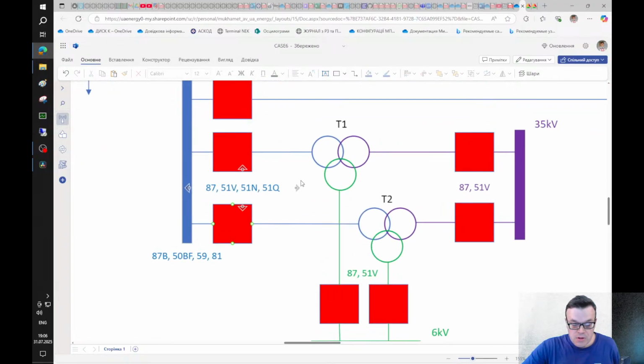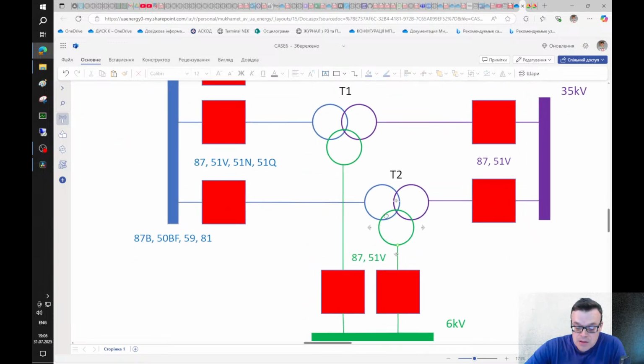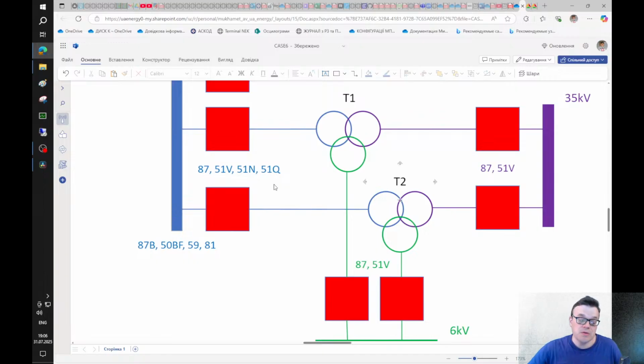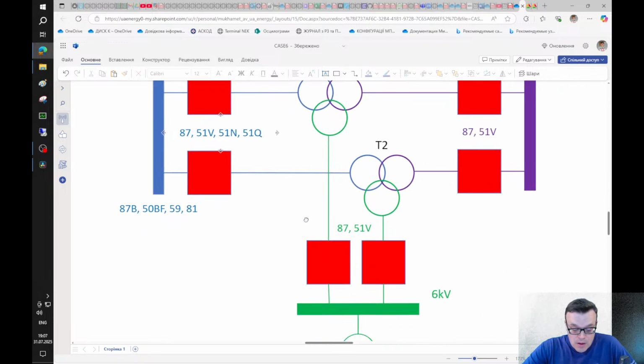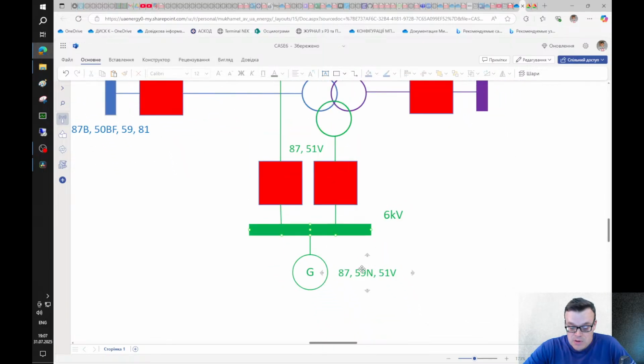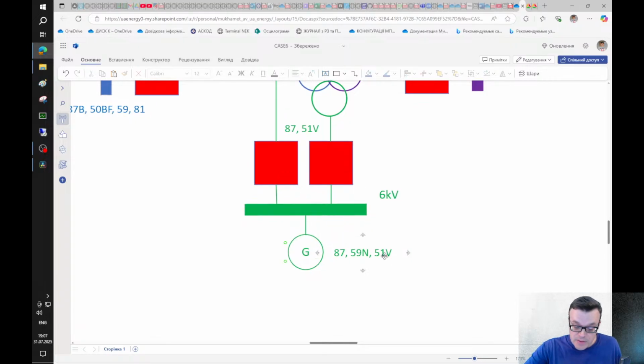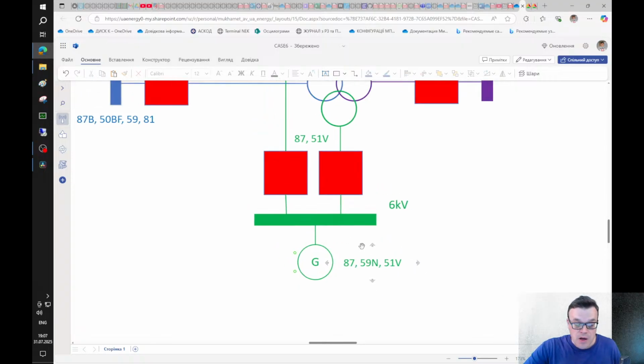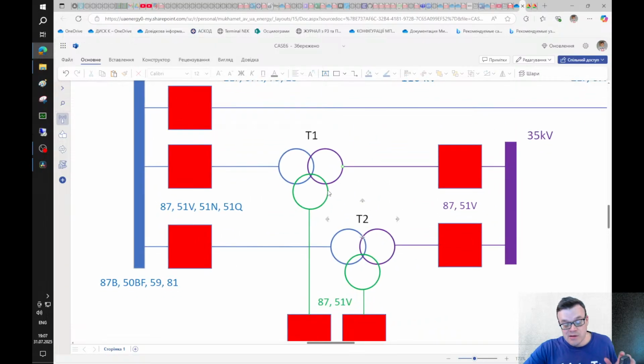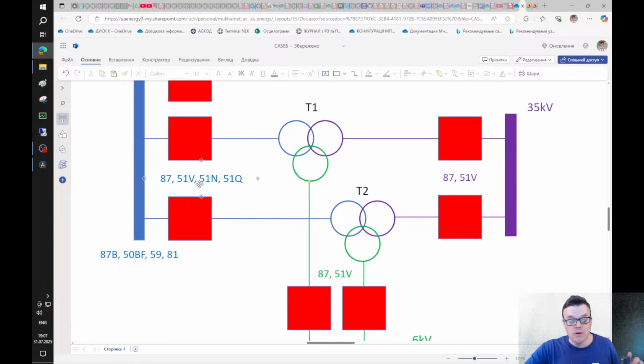Also, we need to talk a little bit about transformer protections. They have differential protection, but mostly all other protections are overcurrent protection. So we have overcurrent protection with voltage blocking, overcurrent protection for ground faults, and this 51Q function is a negative sequence overcurrent protection. The generator has pretty much the same protection functions, and I want to draw your attention to the fact that each primary gear has this 51V function, overcurrent protection with voltage blocking.